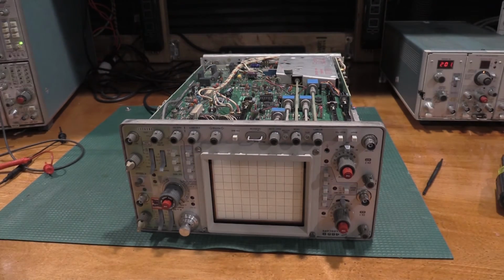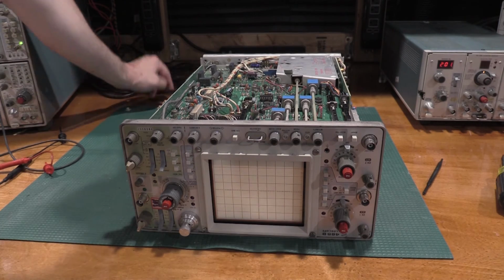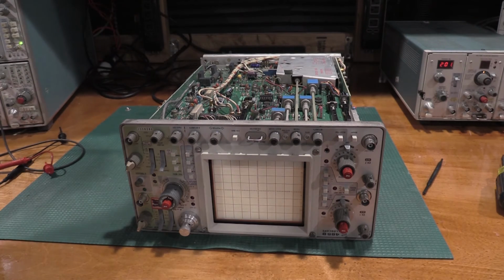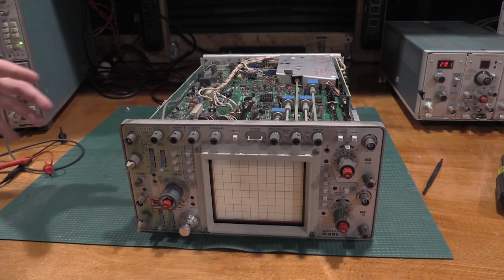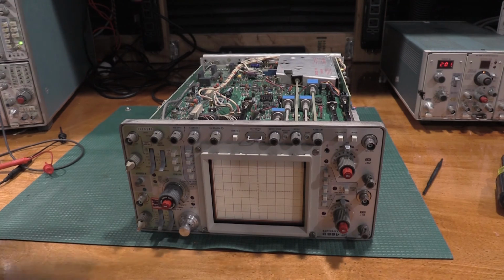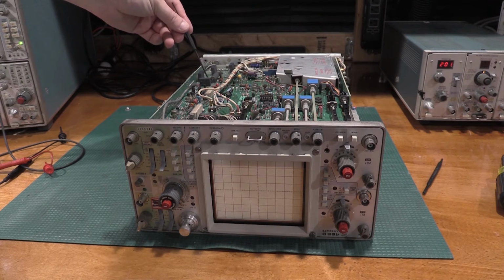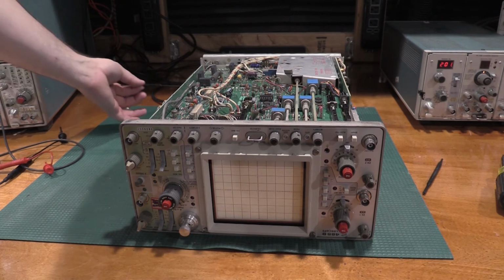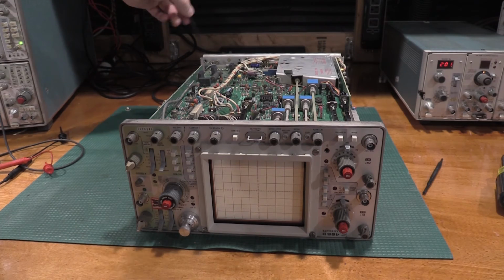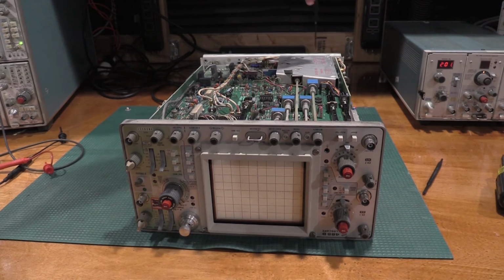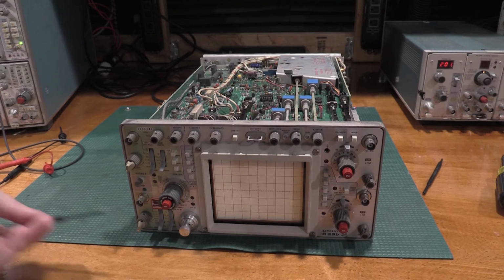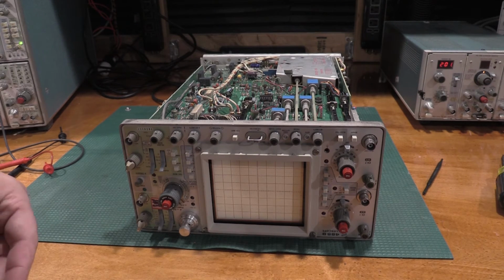Which leads me into one other safety element about doing one of these calibrations. All the adjustment points on this scope are open. We have voltages going everywhere. Line voltage is exposed right here. This is full 110 line voltage. This is where all the rectifiers are. Transformers down here. Line voltage switches back here. High voltage for the CRT is in here. There's a big red wire on the other side that's got 7 kV on it.